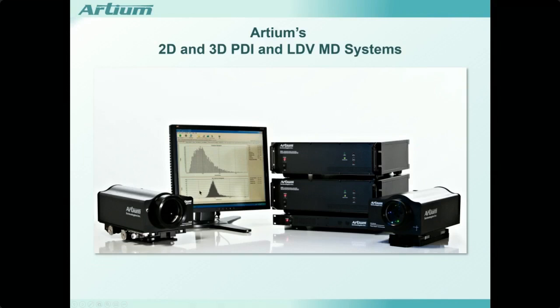Most often, we configure our systems as a separate transmitter and receiver, and that allows the user to position the receiver in some optimum collection direction and get proper measurements. It also can be used in the off-axis backscatter direction if the flow axis demands that. Shown here also are the signal processing devices and, of course, the display of the histograms.